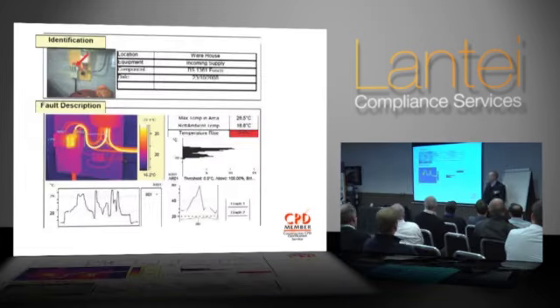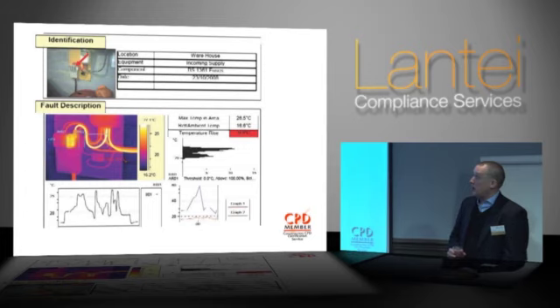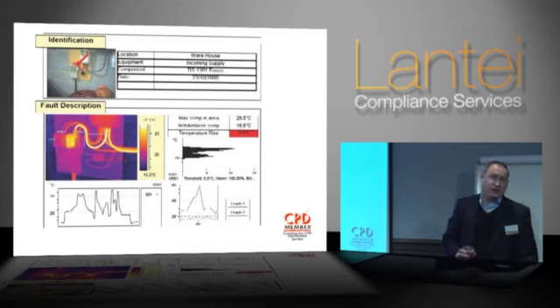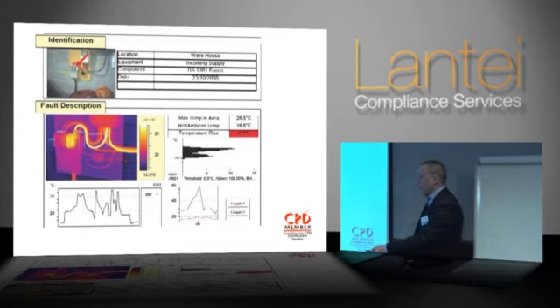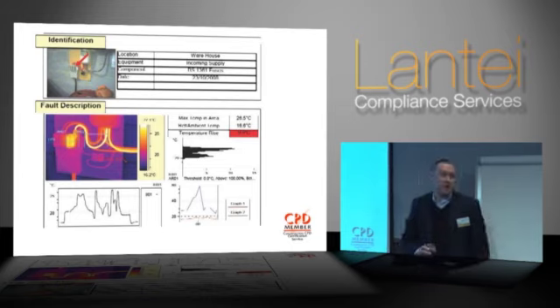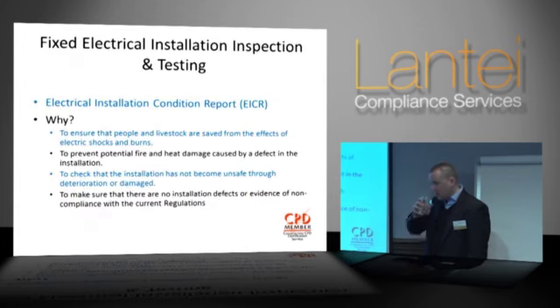When you get mains analysis carried out, what you're looking for is something similar to this in terms of a report: an actual photograph of what's been inspected and imaged, the thermal image itself discussing the temperature rises, and a comment at the bottom telling us what the problem is and what recommendation should be made for dealing with it.